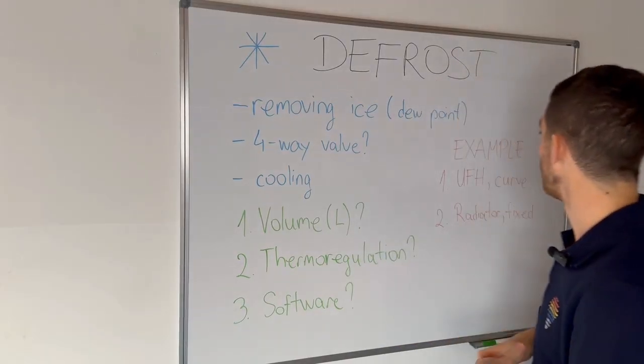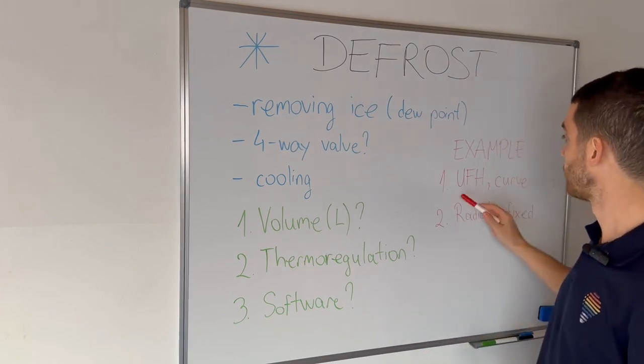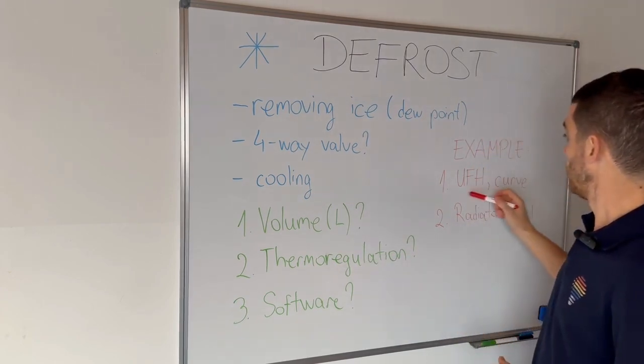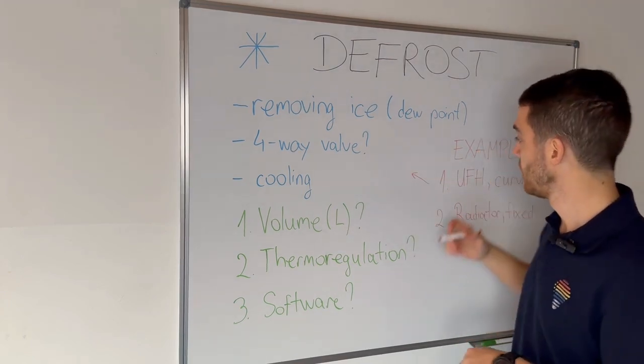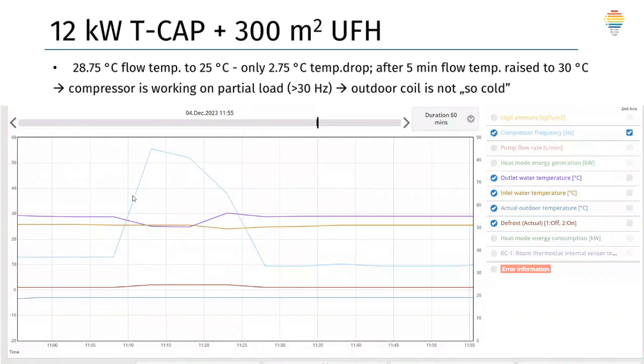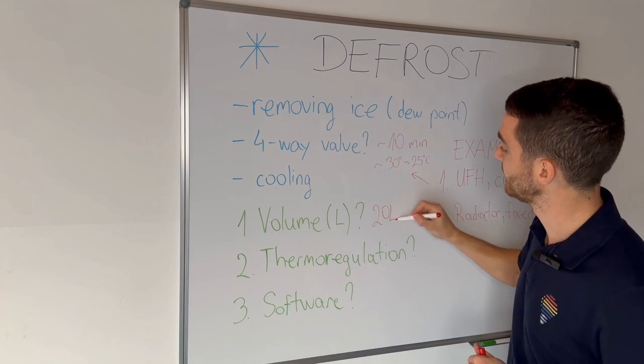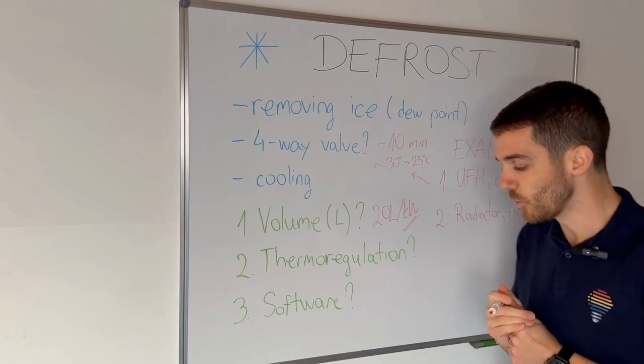Let me show you two examples. First: underfloor heating, a 12 kilowatt unit with around 250 liters of water — all underfloor heating. In that case, with really high humidity, the defrost cycle lasts around 10 minutes. The temperature drop is from 30 degrees down to 25 degrees, and then after 10 minutes it returns to 30. This customer doesn't even know the defrost cycle is happening. This is because we have a huge volume of water. The recommendation is minimum 10 liters per kilowatt, but I would say at least 20 liters per kilowatt — if you ensure that, you will always be on the safe side.